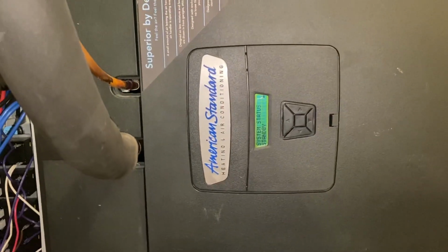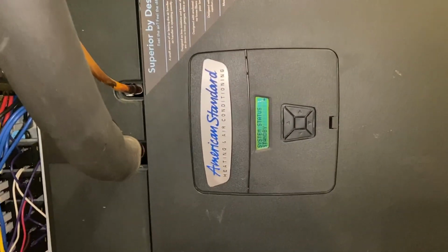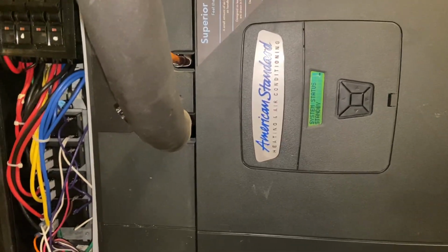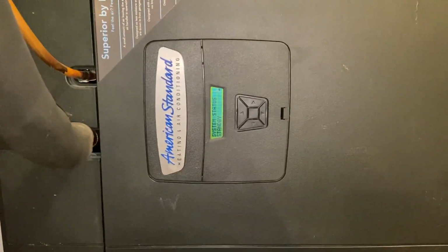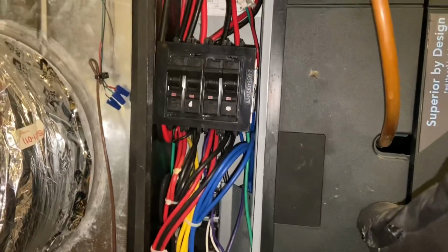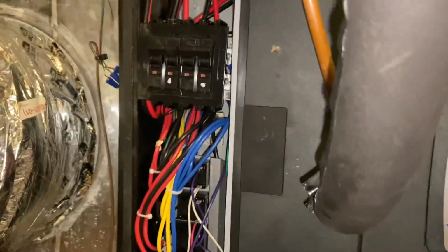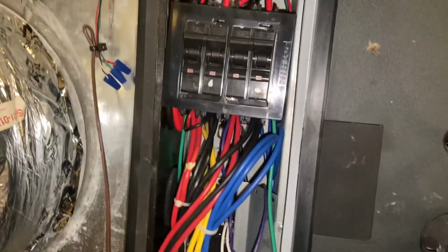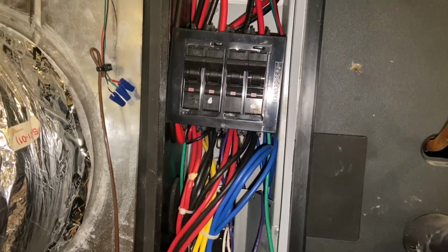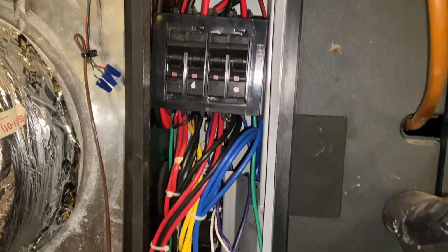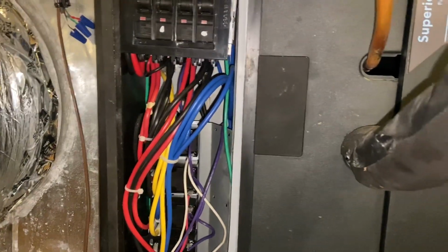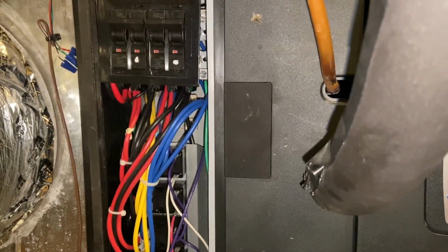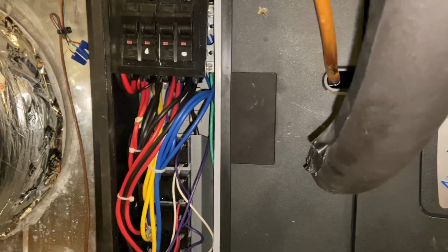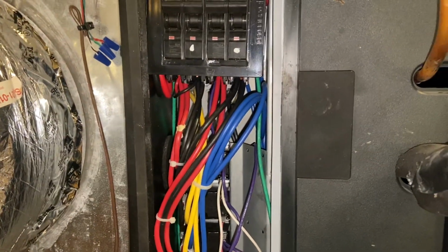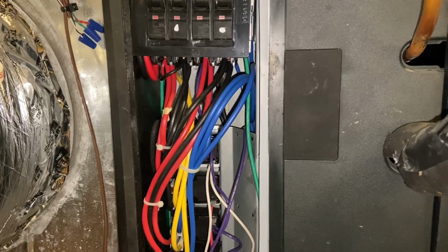For my air conditioning system, I've got this American Standard system. It's a 5-ton unit that runs the whole house. I've got the air handler in here, wired up with a resistive backup heat, 240 volt with a 60 amp and a 50 amp circuit coming in. The outside unit is just a 5-ton heat pump, air-to-air heat pump. And then we have a zoning panel, which I'll show you in a minute.